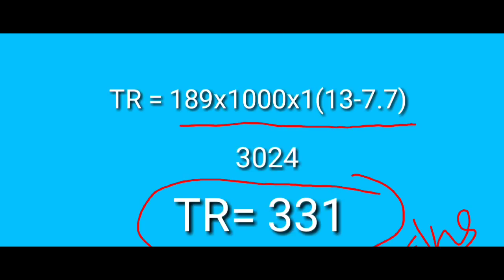For the centrifugal chiller, TR is equal to 189 into 1000 into 1 into (14.6 minus 9.0), divided by 3024. Our total TR value is equal to 331 TR. Next, on the VAM chiller.